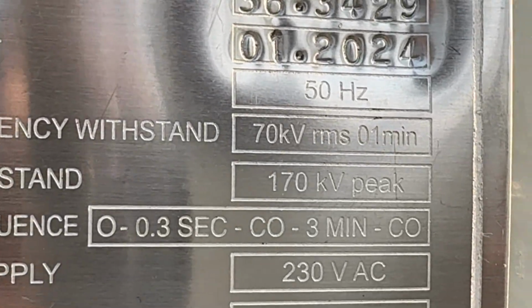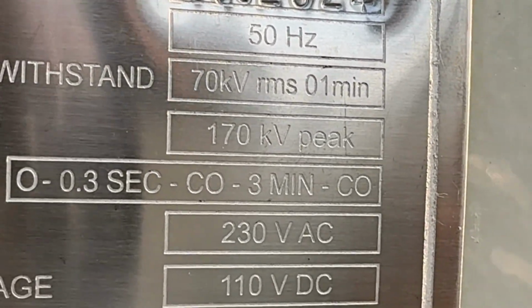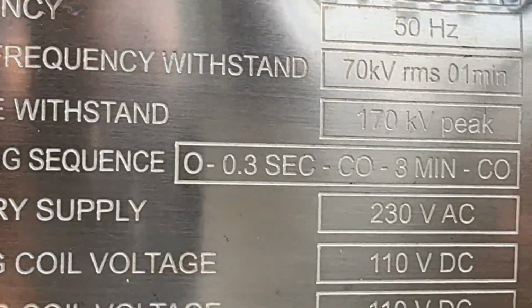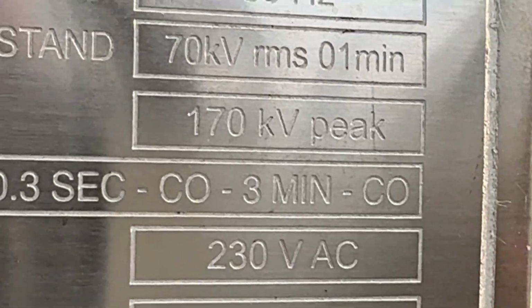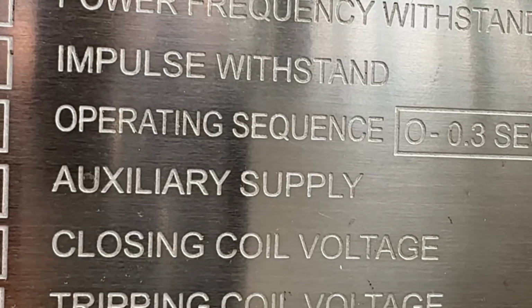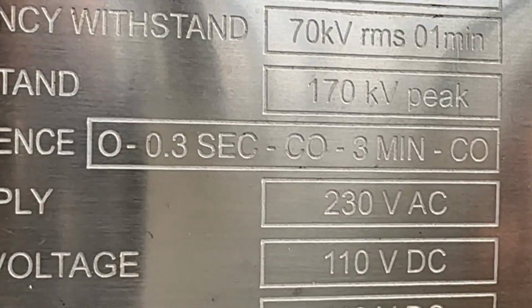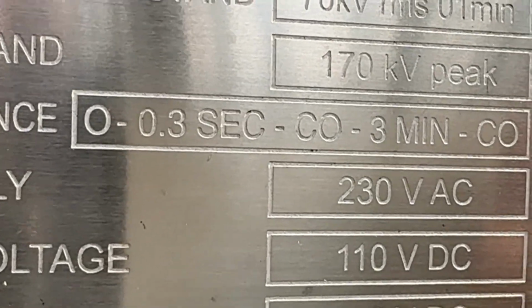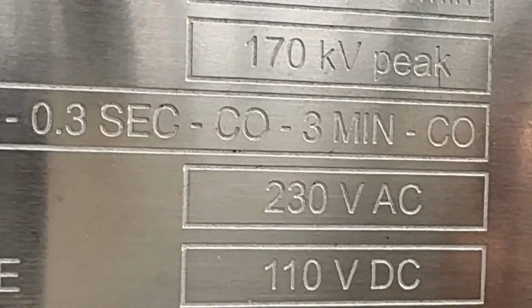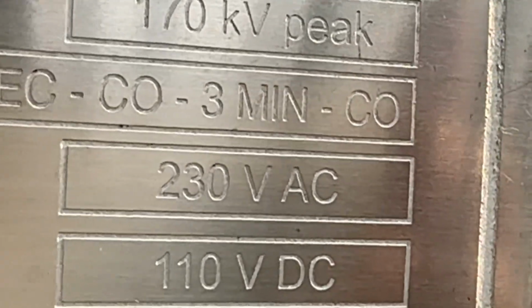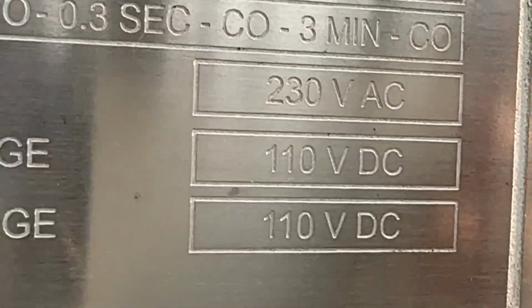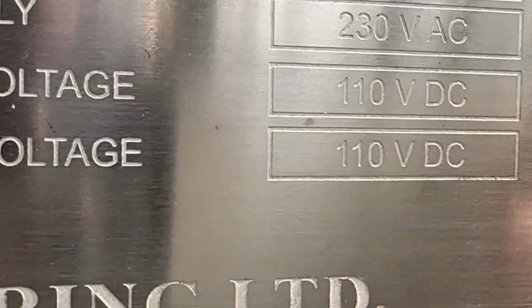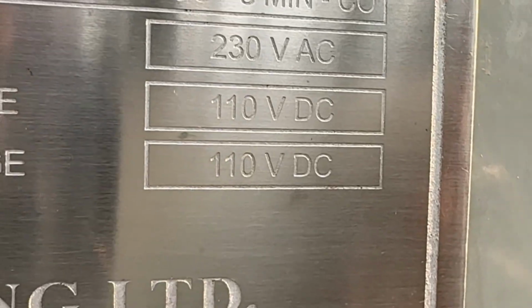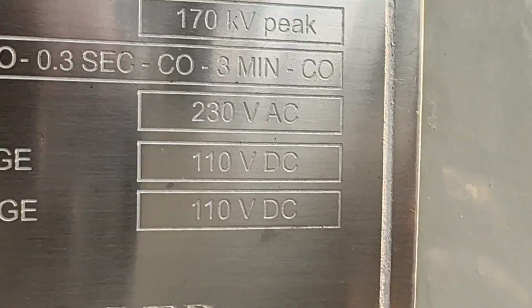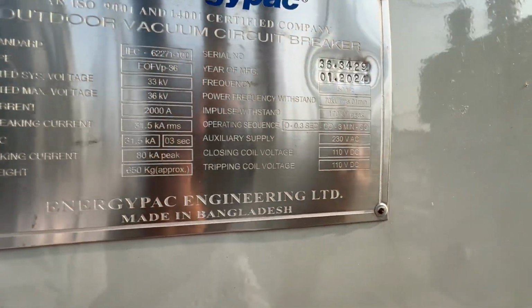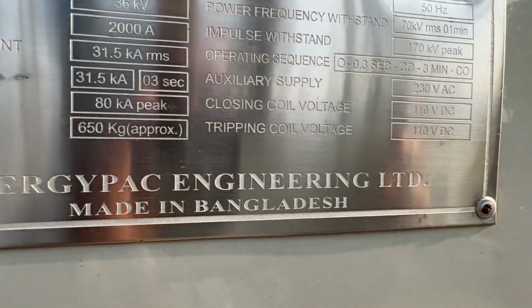Power frequency withstand voltage 70 kV RMS for 1 minute. Impulse withstand voltage 170 kV peak. Operating sequence: open, then 0.3 second, then close, open, then wait 3 minutes, then again close, open. Closing coil voltage 110 volt DC and opening coil voltage 110 volt DC. Okay, this circuit breaker is made by Energypac, Bangladesh.